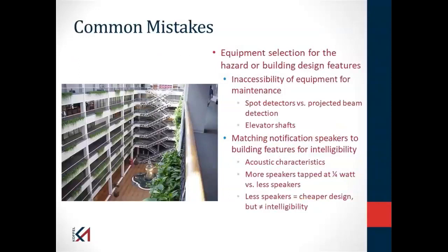Look at this atrium. So historically, people would locate spot-type smoke detectors up on the top of the atrium. NFPA 72 says on an annual basis, I need to access that detector. I need to do a functional test of that smoke detector. How are you going to do it if it's out in the middle of this atrium? Are we going to bring lift equipment in here for people to get to that smoke detector? Or, the fact that we didn't provide access, are they simply going to say, well, we're not going to test that detector at this time.